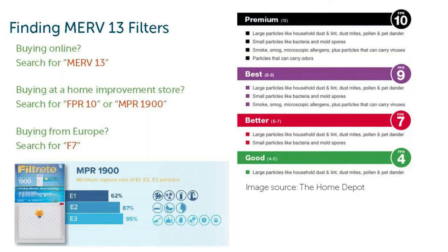Some stores carry filters with their own labeling system, so it can take some digging to find the MERV rating. FPR and MPR are commonly used instead of MERV for filter ratings. FPR stands for Filter Performance Rating and is used on filters sold at Home Depot stores. FPR 10 approximately equates to a MERV 13. MPR stands for Microparticle Performance Rating and is used on filters manufactured by 3M. MPR 1900 approximately equates to a MERV 13.